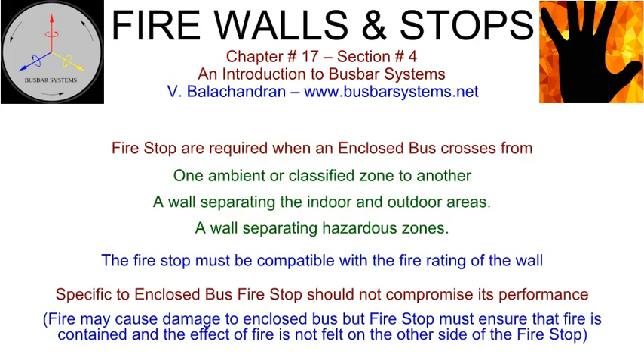It is used when an enclosed bus crosses from one ambient or classified zone to another. It may be specified when an enclosed bus crosses a wall separating the indoor and outdoor areas. It may be specified when an enclosed bus crosses a wall separating hazardous zones. The fire stop must have compatibility with the wall on which it is installed. It cannot have a rating higher than that of the wall.